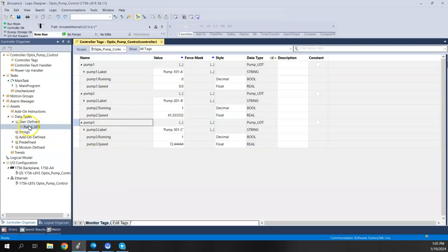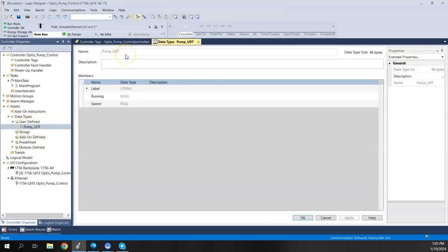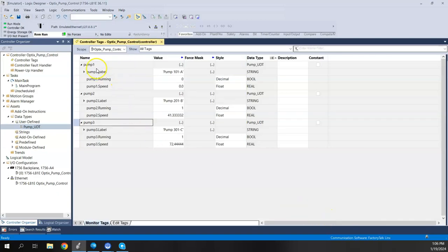We'll come back to Studio 5000 where I've already created a user-defined data type. The example we'll use is a pump faceplate or pump widget. We'll have the same tag structure for each of the pumps in our system, and when we make the pump faceplate in Optix, these common tags will get sent into each instance. Our pump UDT has three tags: 'label' (a string), 'running' (a boolean), and 'speed' (a real data type).